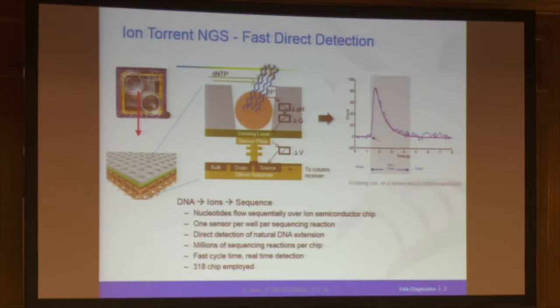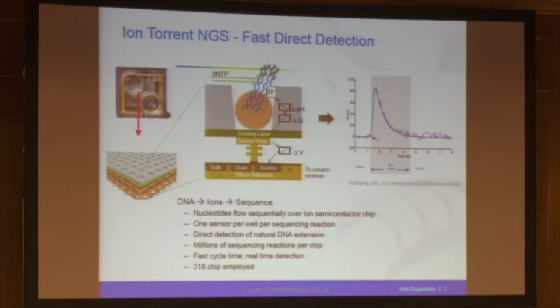Very briefly, you may have attended the plenary session yesterday where we had an excellent talk about technologies and next generation sequencing, so I'm not going into much detail here. Sufficient to say that we are using ion torrent technology originally developed by Life Technologies, and we have licensed that technology. Basically, we're measuring protons released by binding events in the DNA or RNA. pH changes are recorded and translated into sequence information. The main technology part is the 318 chip from Life Technologies, used throughout all our assays in infectious diseases and oncology.